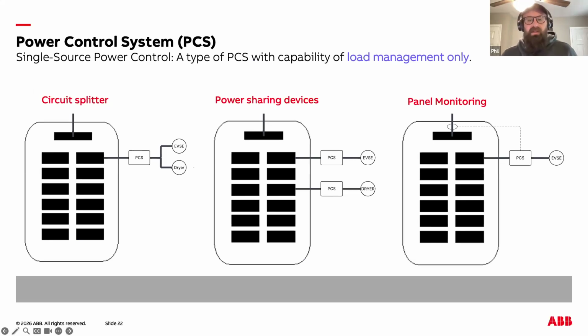On the left, we have a simple circuit splitter, which allows one or another load to operate at any given time. In the center, we have power sharing devices that monitor and control two or more loads to operate within a predetermined power limit. And on the far right, we have a panel monitoring device that monitors real-time power consumption on the service or feeder and allows a load to run so long as there is enough headroom for the load to do so.